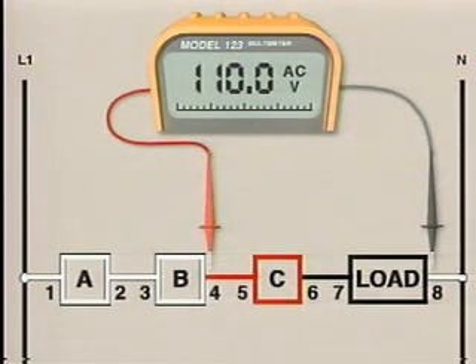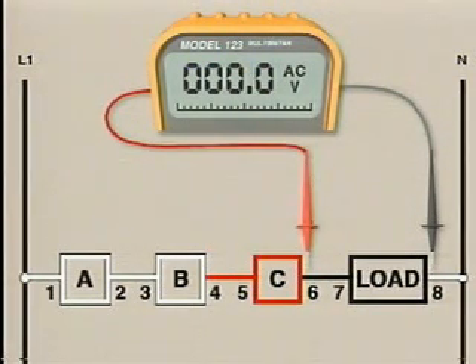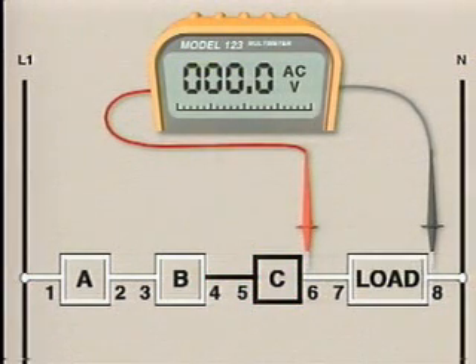Because the circuit's operating voltage is present at test point 4, but not test point 6, the cause of the problem must be between those two test points. Because the cause of the problem is located between test point 4 and test point 6, all of the circuit's components after test point 6 can be eliminated as possible causes of the problem. The last check that we need to make should split the remaining portion of the circuit in half. So we'll check the voltage at test point 5. This test will tell us if the wire between test points 4 and 5 is good.